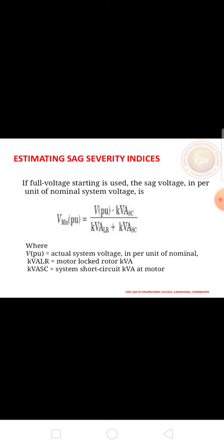Most equipment uses the RMS voltage as a function of time as the only event characteristic. Next, the calculation of severity indexes. First one, for full voltage starting, the sag voltage is used in per unit of nominal system voltage, that is, V minimum per unit equals V per unit times kVA short circuit divided by kVA short circuit, plus kVA locked rotor. Here V per unit equals the actual system voltage in per unit of nominal, kVA LR equals the motor locked rotor kVA, and kVA SC equals the system short circuit kVA at the motor.